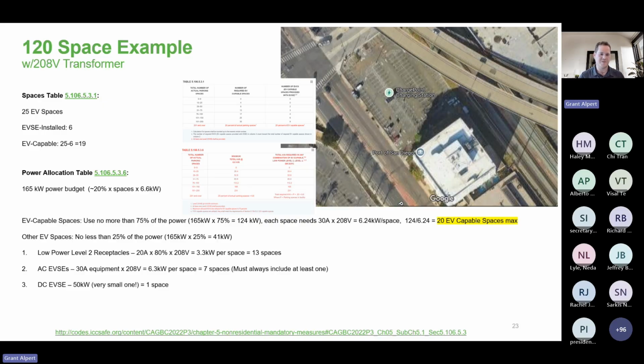And then 25 minus 6, you have 19 that have to be EV capable. So that's the conduit and the panel capacity. If we go differently, if we use the power allocation method, the budget that has to be met is 165 kilowatts, so 20% times 120 times 6.6 kilowatts gets that 165. Of that 165 kilowatts, no more than 75% can be EV capable, which works out to about 124 kilowatts.